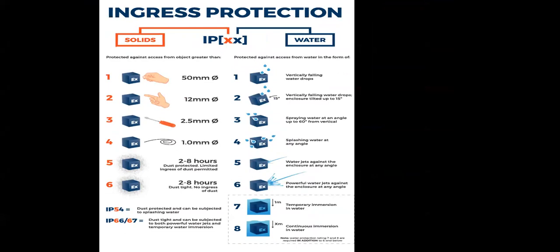What does ingress protection mean here? We always see it as two digits, which is why it is written XX. The first X stands for solids and the second X stands for water. So if I say it is 1-1, that means that particular panel or DB or element is protected against 50 mm solids and vertically falling water drops.